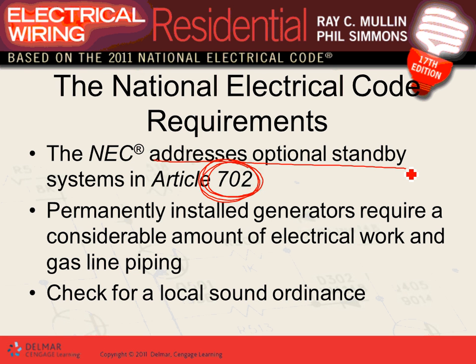Okay, permanently installed generator: check for local sound. There's something called a sound ordinance. Now, Adam, if you decided to put a 50 kW generator in your backyard, and that baby starts humming, and your neighbors start calling the city, that's noise pollution. When you put in a generator, guys, typically if you have 10 kW or less in dwellings, nobody worries. But if you have a commercial building in a dwelling area, be very aware that you will have noise issues. How do you solve the noise? They have attenuation enclosures. They put them in an enclosure that attenuates, minimizes, neutralizes the noise. That's how they solve the problem. That becomes a major issue, guys, when we talk about sizing generators for the commercial industrial building next project. When we bring our friends from Kohler and they talk, Jerry will be talking a lot about the sizing, or how do you pick an enclosure for noise attenuation, as they call it. Okay, so when you size a generator, pay attention to the noise.